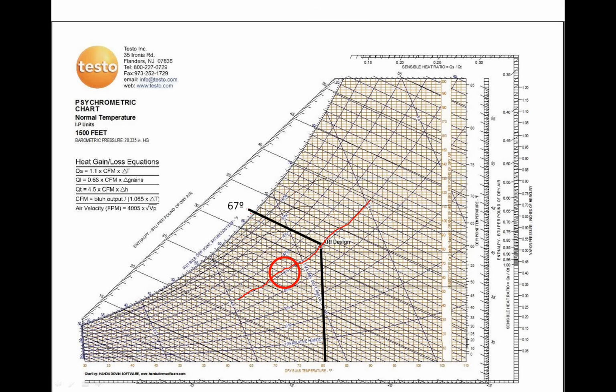Wet bulb simply takes into account heat and humidity, because an air conditioner removes two types of load. It removes sensible load, which is heat, and it removes latent load, which is humidity, right? So the humidity plays a big impact on how the system performs. The higher the humidity is, the more work goes into converting water vapor in the air into water. So when the humidity is very, very high in a home, most of the work the air conditioner is doing is dehumidification. As the humidity drops in a home, more of the work goes to cooling it or dropping the temperature. And we'll go over some of those relationships in the next couple slides here.